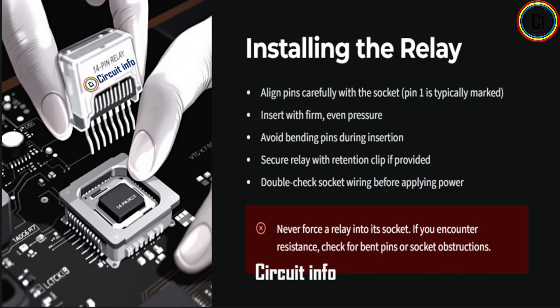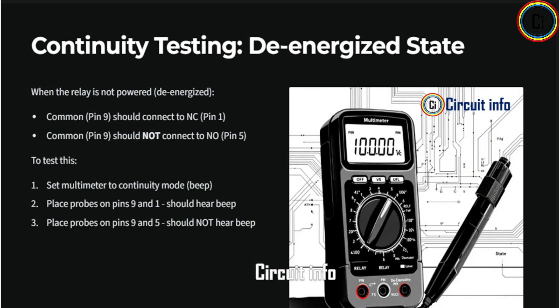Testing a 14-pin relay is simple. Check the coil resistance between pin 13 and 14, test contacts using a multimeter in continuity mode, verify wiring in the relay circuit, and always ensure the contact rating matches the load current.